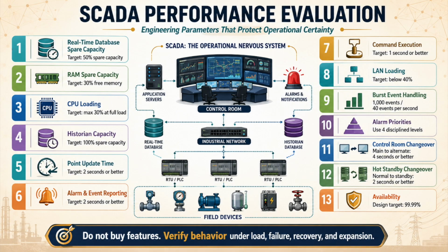2 seconds or better from source event to operator visible alarm should be treated as a serious requirement subject to field communication constraints, and sequence must be preserved because during abnormal operation, what happened first can be as important as what happened at all. Therefore, source-to-screen latency, burst conditions, communication recovery, timestamp accuracy, and event journal integrity must be verified.